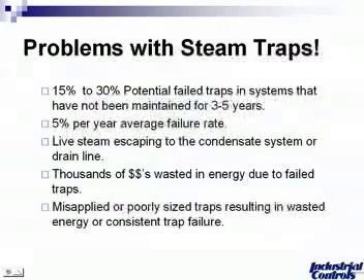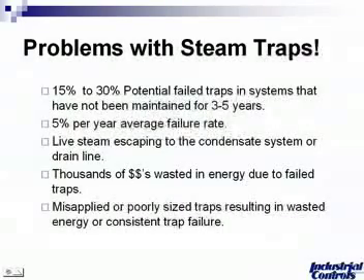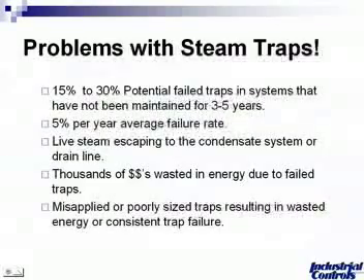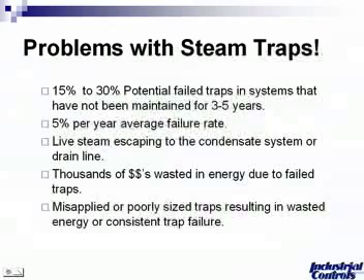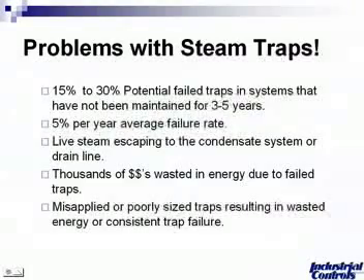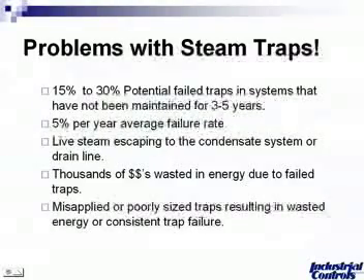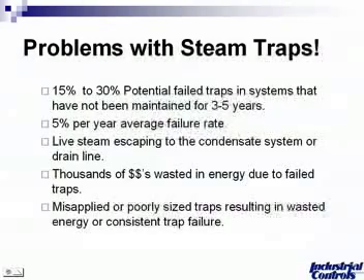What kind of problems do we have with steam traps? In a system, 15 to 30 percent of traps may have failed in systems that have not been maintained for three to five years — that means a five percent per year average failure rate — with live steam escaping to the condensate system or drain line, thousands of dollars wasted in energy due to failed traps, and a major part of it being misapplied or poorly sized traps resulting in wasted energy or consistent trap failures.